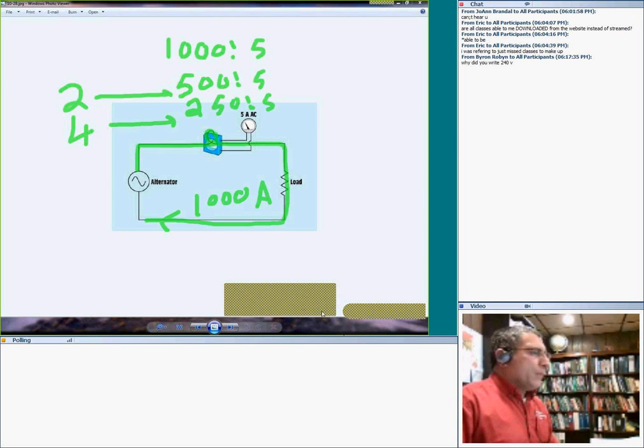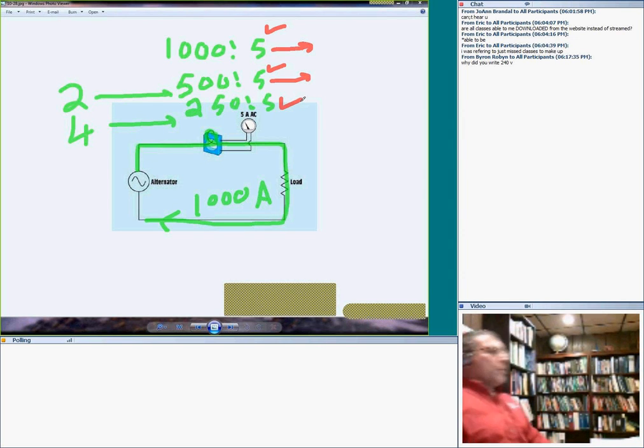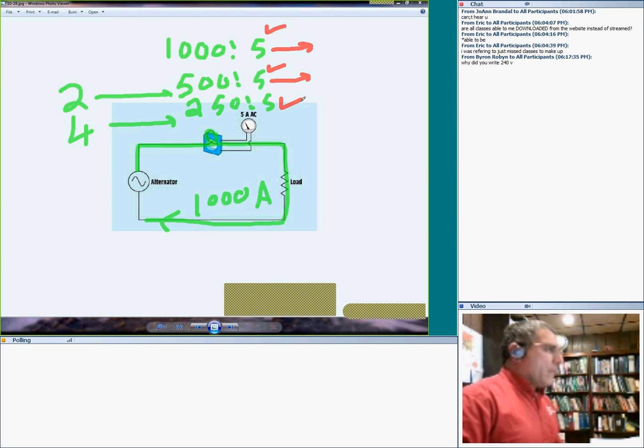What we do as engineers and designers instead: if I know my switchgear is 1000 amp, I just buy a 1000 amp CT. If I know I'm dealing with 500 amp, I buy a 500 amp to 5, or 250 to 5. That's what I normally do for major equipment.